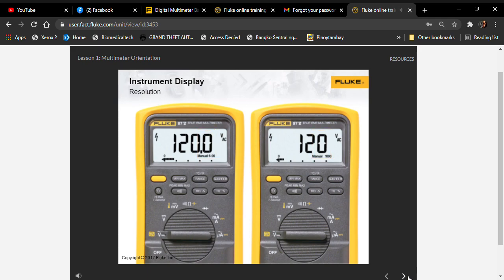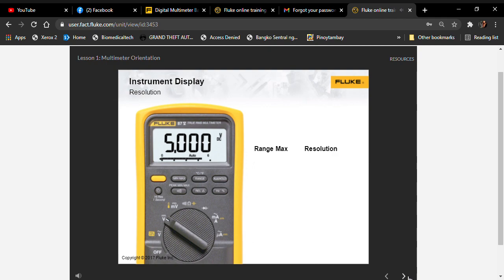This is the resolution. The value of this digit depends on the location of the decimal point, so resolution depends on the range. For example, in the 0 to 600 volt range, the display shows values from 0.0 volts to 600.0 volts. The rightmost digit represents 0.1 volts or 100 millivolts. In the 0 to 6 volt range, the display shows values from 0.000 V to 6.000 V. The rightmost digit represents 0.001 volt, or 1 millivolt, 1/1000th of a volt.